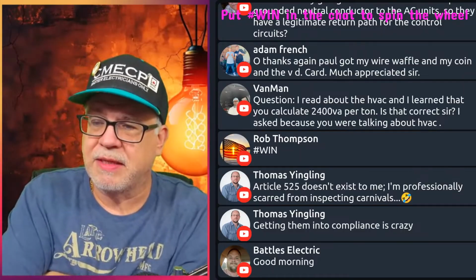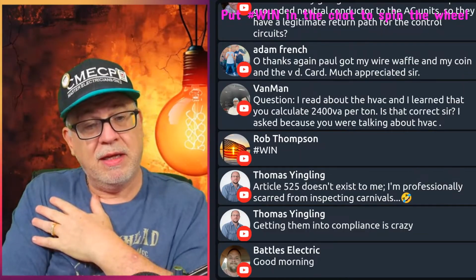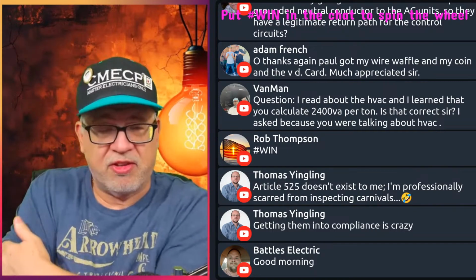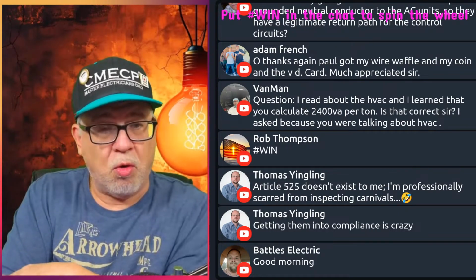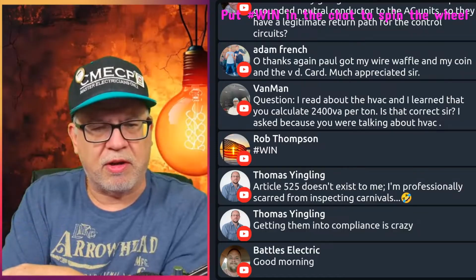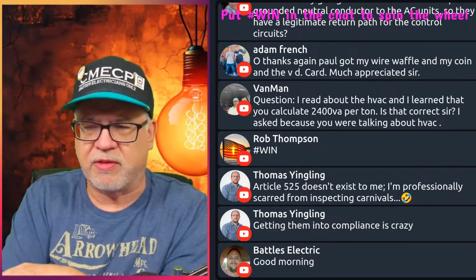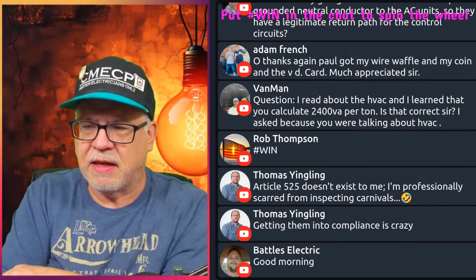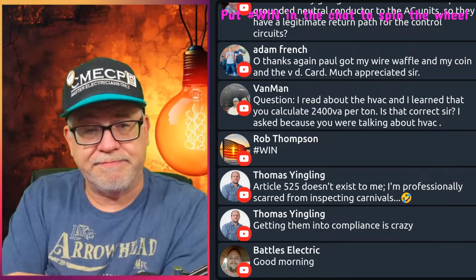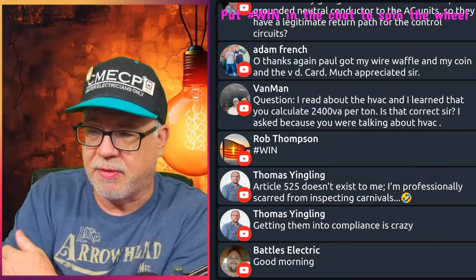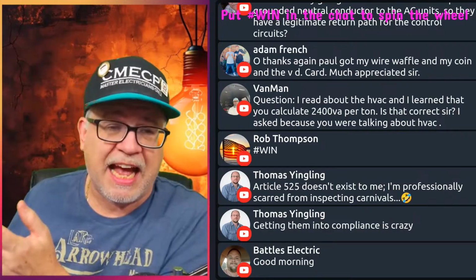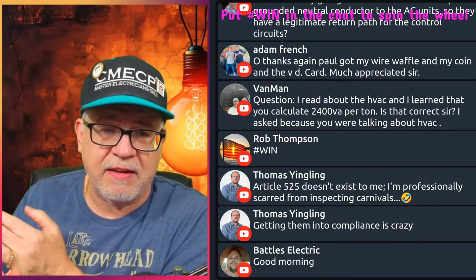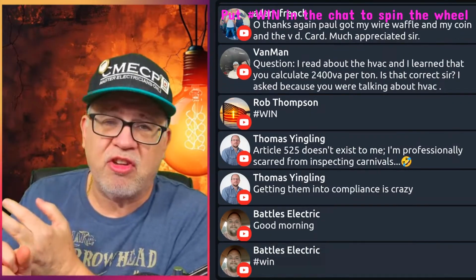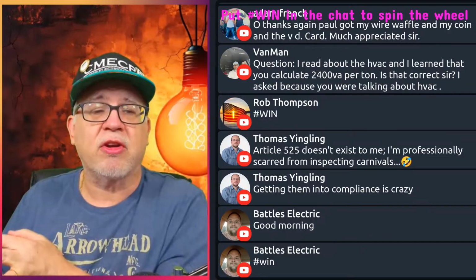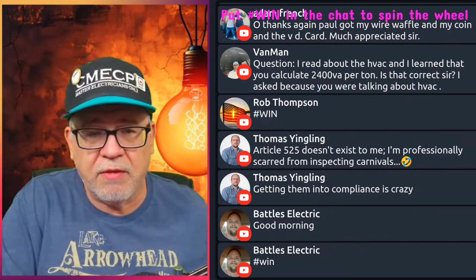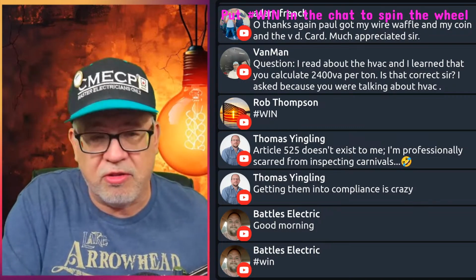So anyway, what's going to happen, I believe, is that you're going to have GFCI, either a standard GFCI or an SP GFCI. It just has a higher milliamp threshold. It can handle higher inrush and frequency. I believe that those are going to be required. And I believe the manufacturers are going to have to scramble, because the CCID that's built into a lot of these EVSEs, the protection system, as well as any GFP that's built into them, are not going to meet the requirement, in my opinion, of an SP GFCI or a standard GFCI.